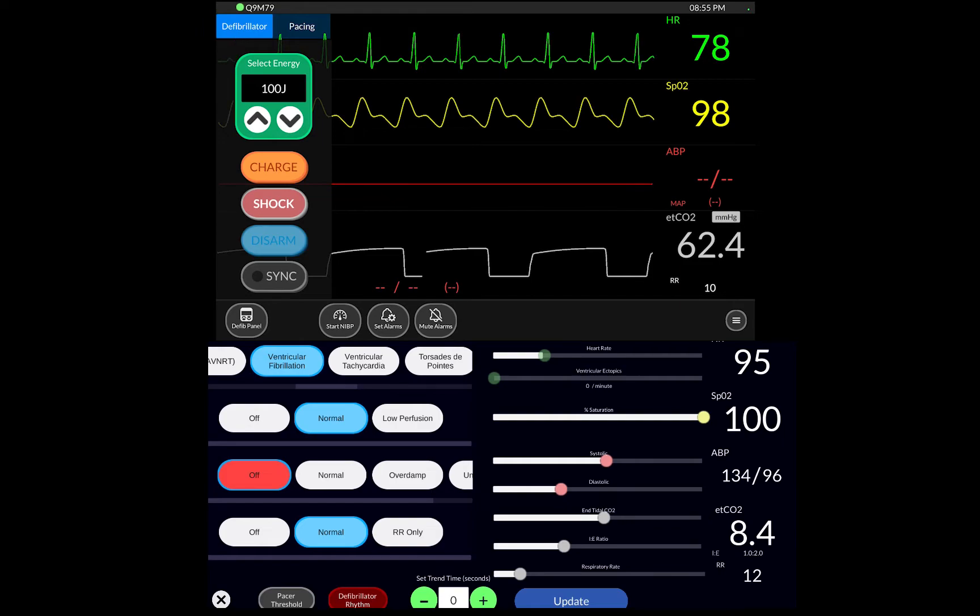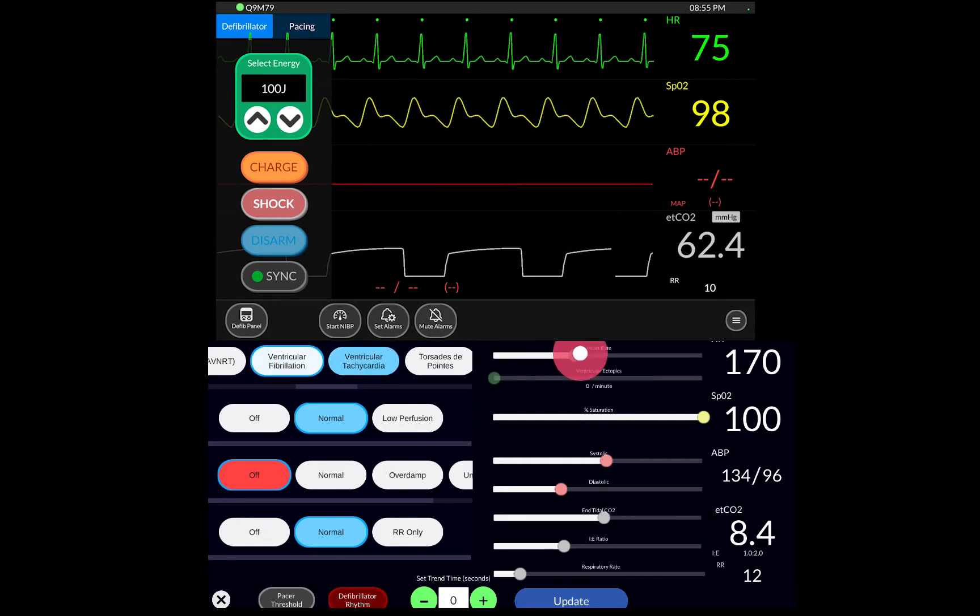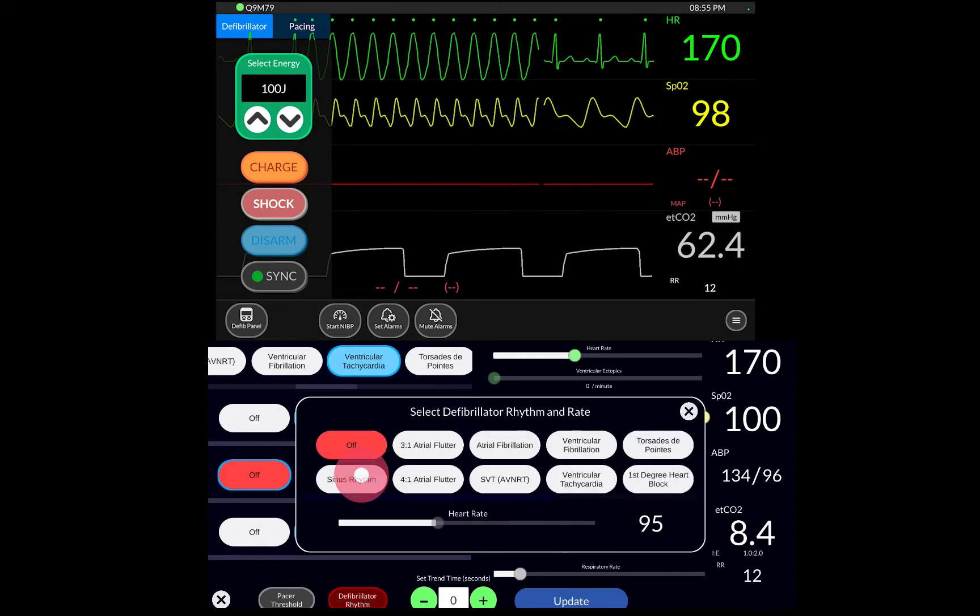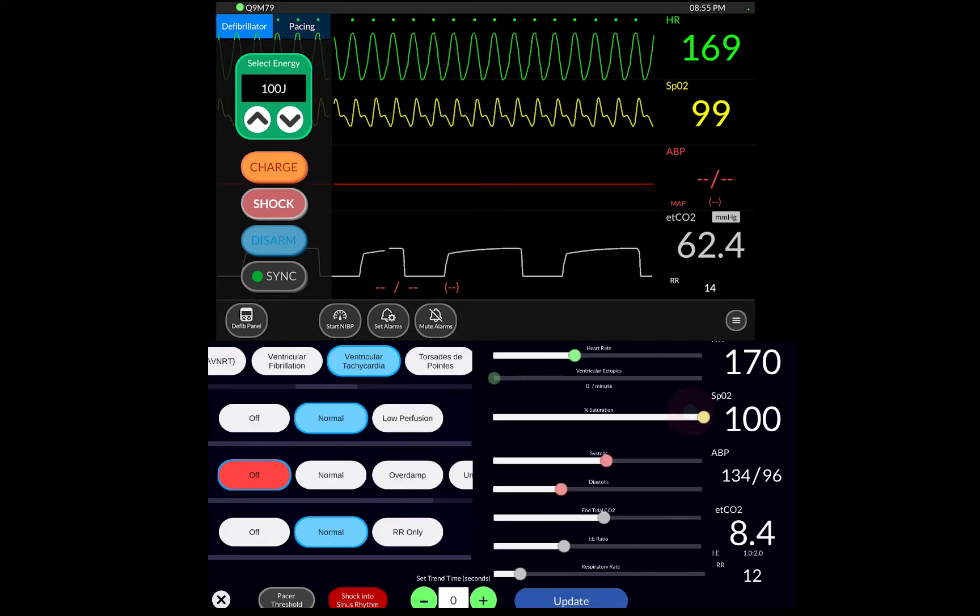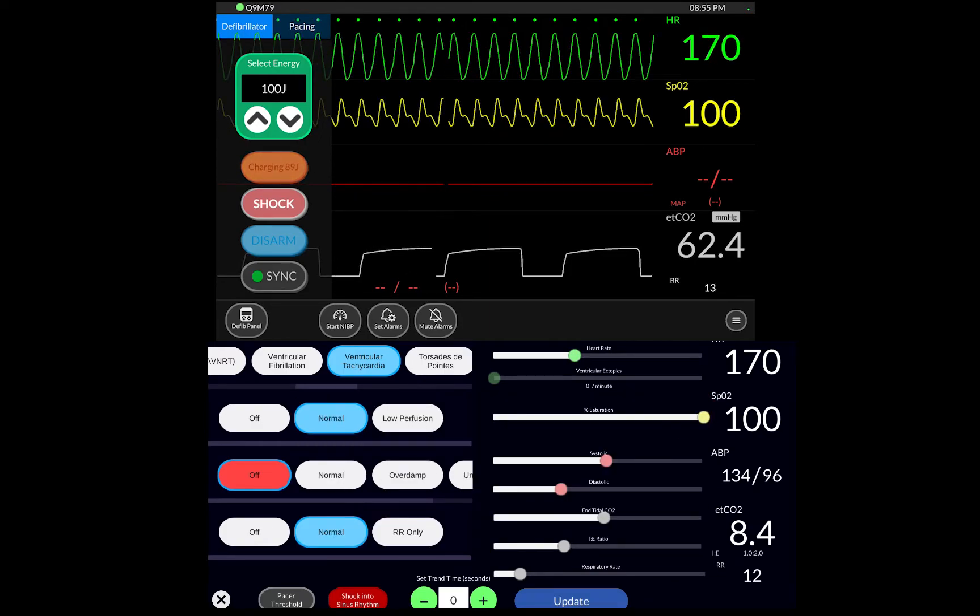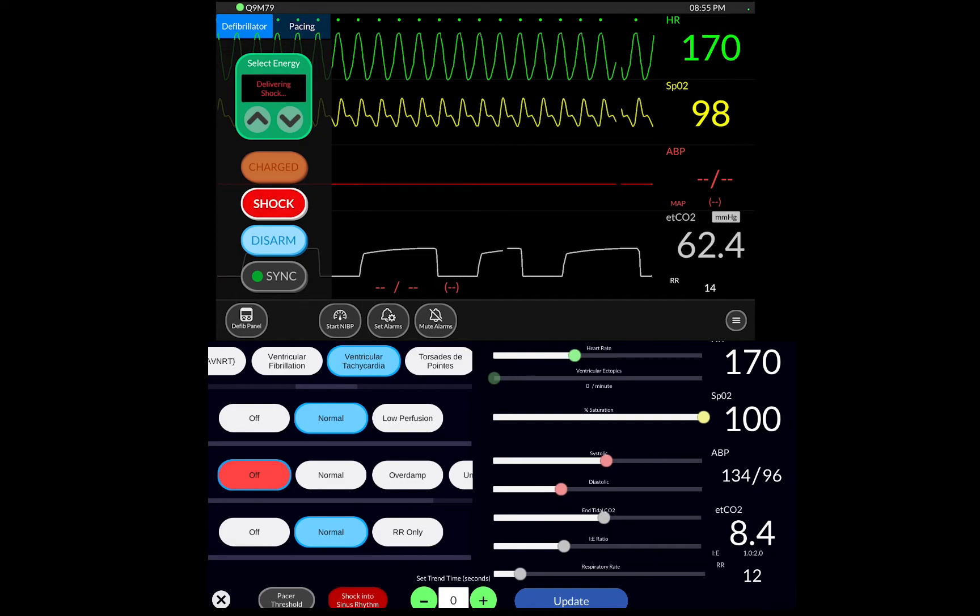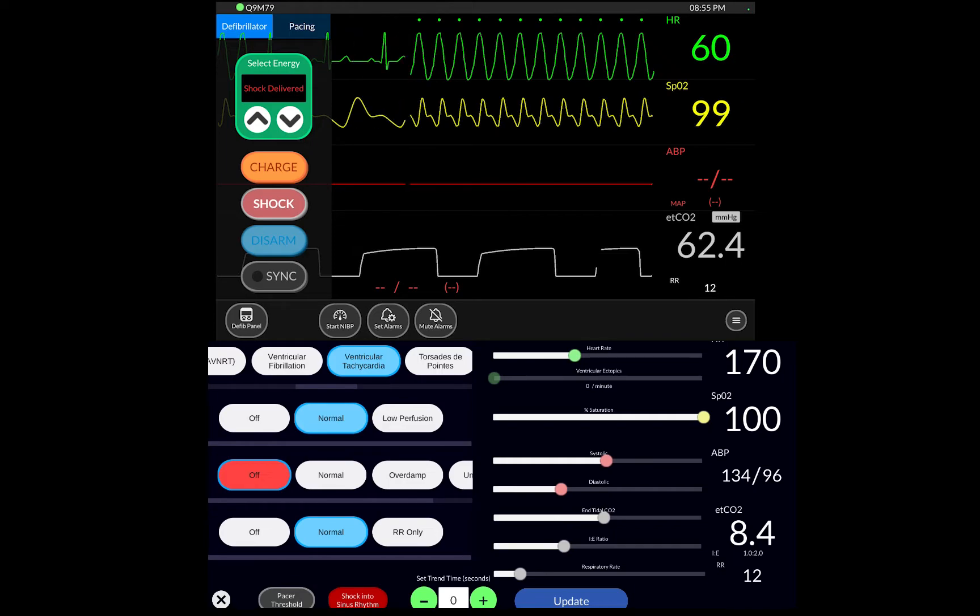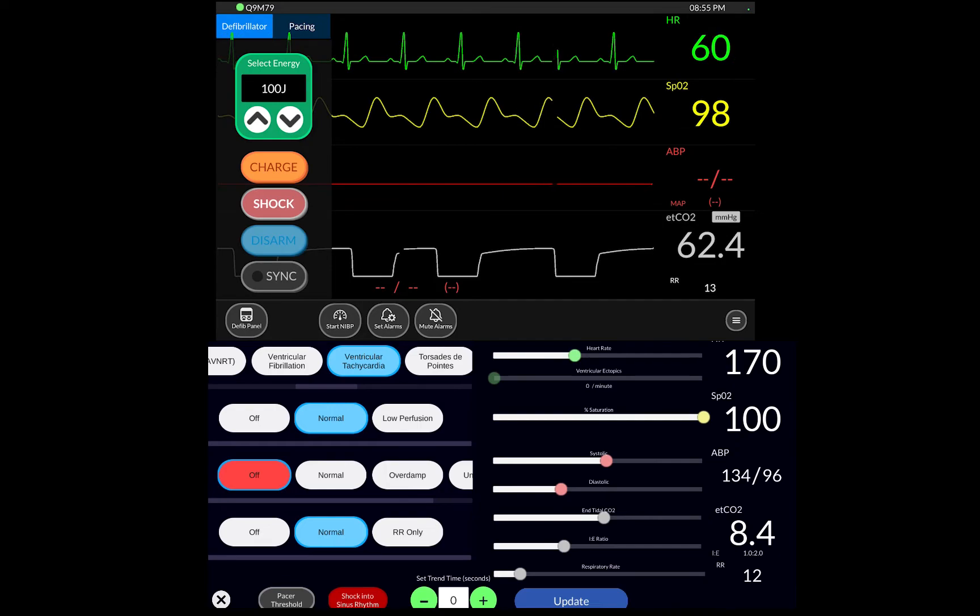And obviously there's the sync button. You can sync and then you see all your markers at the top. So if you were in a VTAC, we can then say after the defibrillator we want to go to normal sinus. We're going to charge and we are synced. So we synced charge, defibrillator dropped and it's been there. We have performed a synchronized cardioversion, which has cardioverted it into a normal sinus. So that is how you would perform something like that.